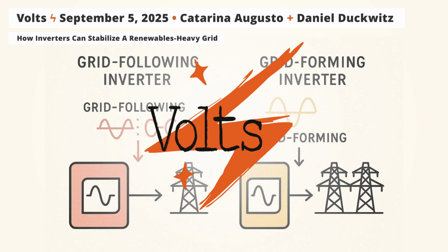Yeah, there is one part where you would basically have to renew the grid connection approval. So you'd repeat all the engineering regarding grid connection and grid code compliance for the retrofit, to get permission from the network operator to do it. It is feasible, and we have done it, so it is not impossible.